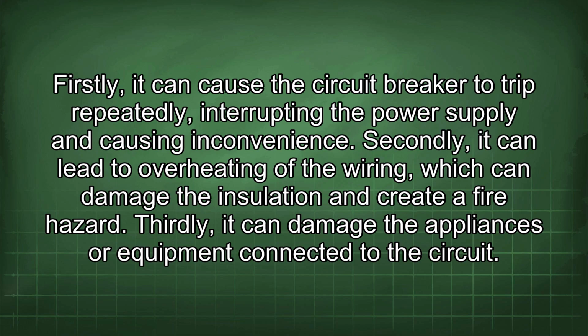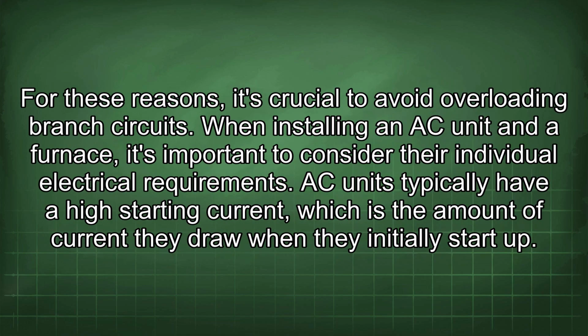Firstly, it can cause the circuit breaker to trip repeatedly, interrupting the power supply and causing inconvenience. Secondly, it can lead to overheating of the wiring, which can damage the insulation and create a fire hazard. Thirdly, it can damage the appliances or equipment connected to the circuit. For these reasons, it's crucial to avoid overloading branch circuits.